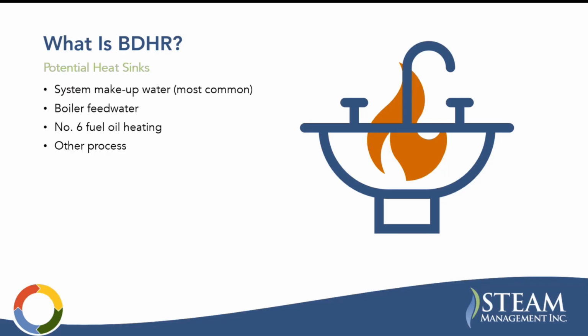As well as the flash steam. If you have a low pressure steam system in the area, you can flash steam off and use it in that system. It doesn't have to be used in the deaerator. It just so happens that the deaerator is typically going to require more steam than you have available in the blowdown system, and so it is a good constant user of the steam and a good application.